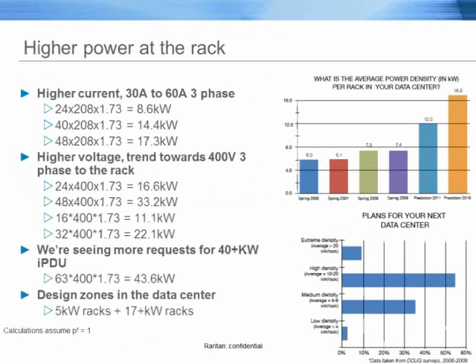So traditionally, we used to see a fight from bringing customers in from even 120 into single-phase high line, 208. Now we've seen that fight to bring customers in from 208 into three-phase. And once you show them the amount of power we can bring in with traditional three-phase, it's kind of amazing. Using our simple math, volts times amps, we're multiplying it by 1.73 for three-phase power. We can bring in 8.6 on a 24 amp PDU, 14.4 on a 40 amp PDU, 17.3 on a 48 amp PDU.